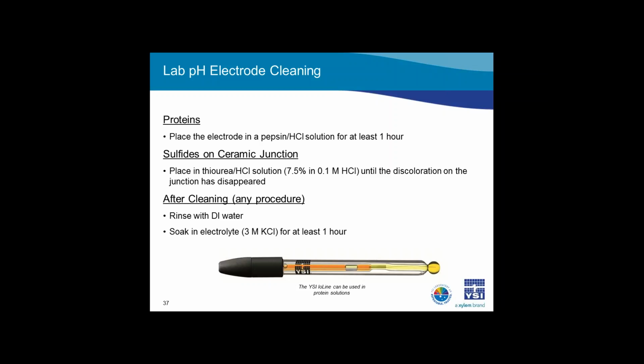So if you suspect organic debris, rinse the electrode with an organic solvent such as ethanol or acetone. And as I mentioned, make sure there aren't any chemical incompatibilities between the solution that you choose, the strength of that solution, and the body of the electrode that you're trying to clean. So take some time to make sure that you're not going to use anything that's going to degrade or eat away at the body of your probe. Next, carefully wipe the glass bulb with a chem wipe or other lint-free soft cloth. Now on to proteins. If you suspect the junction is clogged from proteins, try soaking the electrode in a pepsin hydrochloric acid solution for at least 1 hour.